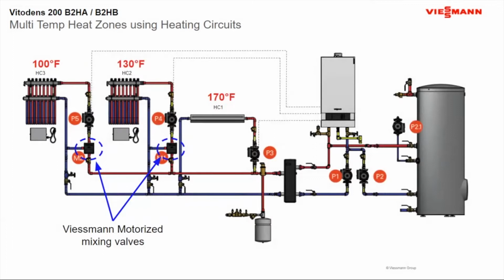So now with the Viessmann mixing valves, it comes, like I said, with a box, just like that AM1 module. It also comes with a boiler supply sensor. I'm sorry, a piping supply sensor, and a place to land your pump, as well as power your 3-way mixing valve. And then all you're sending over from your 3-way mixing valve box is that 145 communication over to 145 on the boiler. Or if you had multiples like this, you could take it from this 145 to this spare 145, and out of this one over to the boiler. It now knows it has 2 mixing valves tied to the boiler.